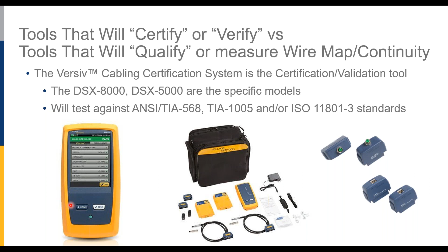Pardon this commercial plug, but here's an important consideration: the difference between tools used to certify cabling, as we say in the telecommunications world, versus what's often called verifying cabling in the industrial environment. A DSX 8000 or DSX 5000 is a tool that can measure against the standards the Ethernet application requires, looking not just for continuity but also noise on the cable.